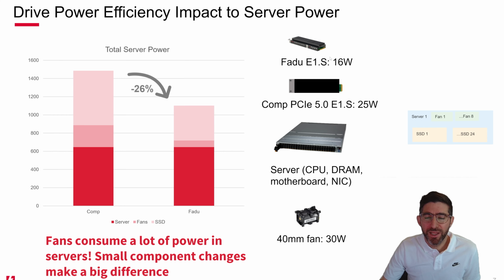So the comparison we're making right here is running a drive at 16 watts. We'll just say a theoretical competitor is running their drive at 25 watts. Again, that's the max. We picked a Supermicro server. This is a dual Sapphire Rapids or Emerald Rapids Intel CPU platform, and it supports 24 E1.S, and these are full PCIe Gen 5 by 4 E1.S. So it supports 15 millimeter or 9.5 millimeter, I think 24 drives across this. And in the server power, I'm calculating CPU, DRAM, motherboard, and NIC, and I'm just assuming the maximum CPU power, where I think I picked a 32 core.